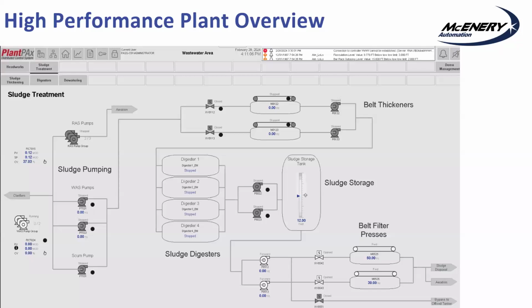I've included a couple of screenshots of high performance HMIs using Rockwell's Plant PAX, and I'll walk through some of the features we've included to make life easier for operators and make sure they get the information they need efficiently. These screens are developed using the ISA 101 standard, which basically uses a grayscale to show the pumps and valves that are not running as dark gray.